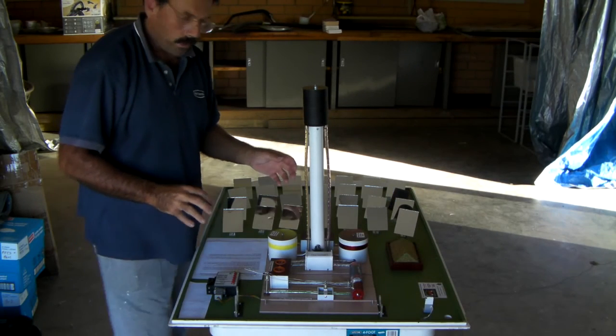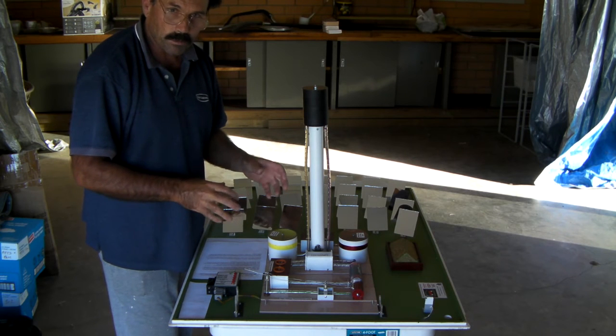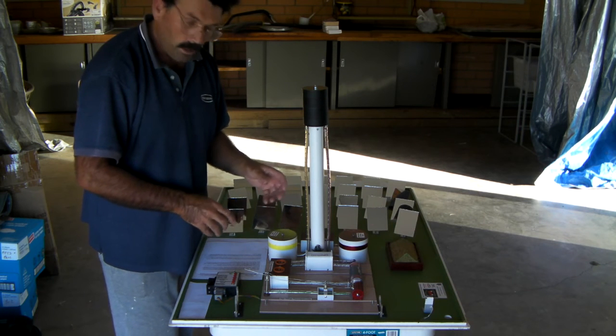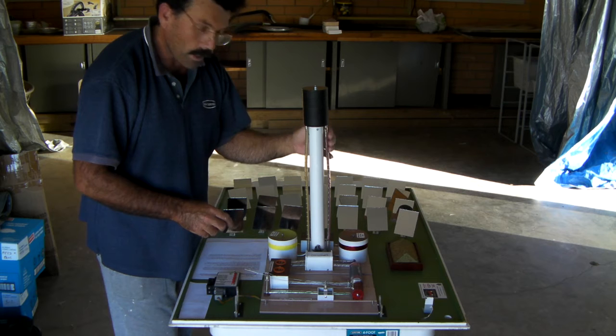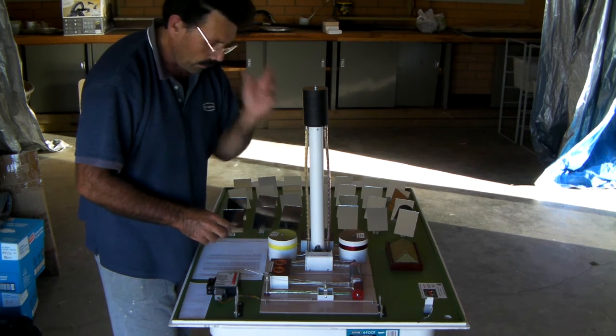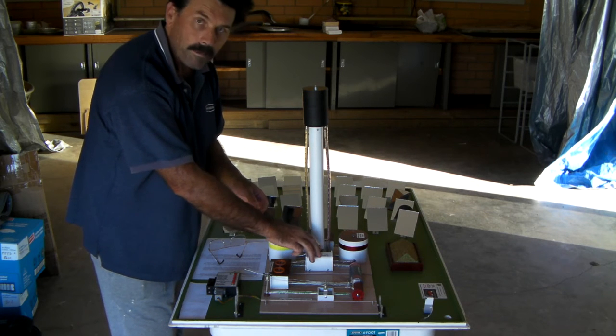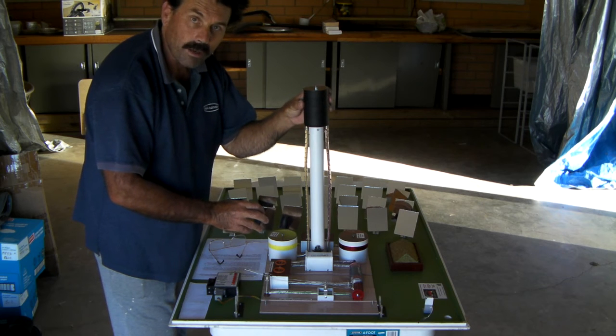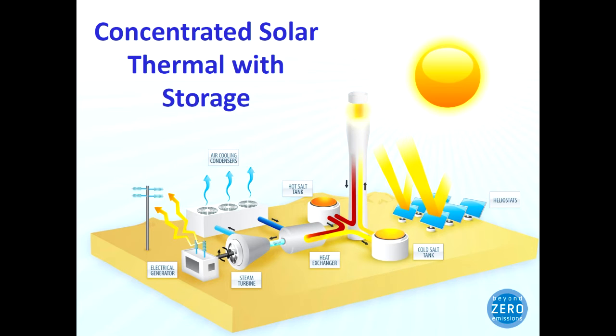So there are four main parts to the salt cycle. On this plant you've got two closed loop systems: one's the closed loop salt cycle and the other one is the closed loop water cycle. On the closed loop salt cycle, we heat the salt to 570 degrees Celsius here. We then pump that hot liquid salt down the tower and store the energy in the tank. Then we run the hot salt through a heat exchanger so it gives up its heat to the water, and then back into the cold tank at 290 degrees Celsius, and then back up to the receiver to get to 570 degrees Celsius again. So there are four main parts to the salt cycle: the receiver, the hot tank, the heat exchanger, and the cold tank.